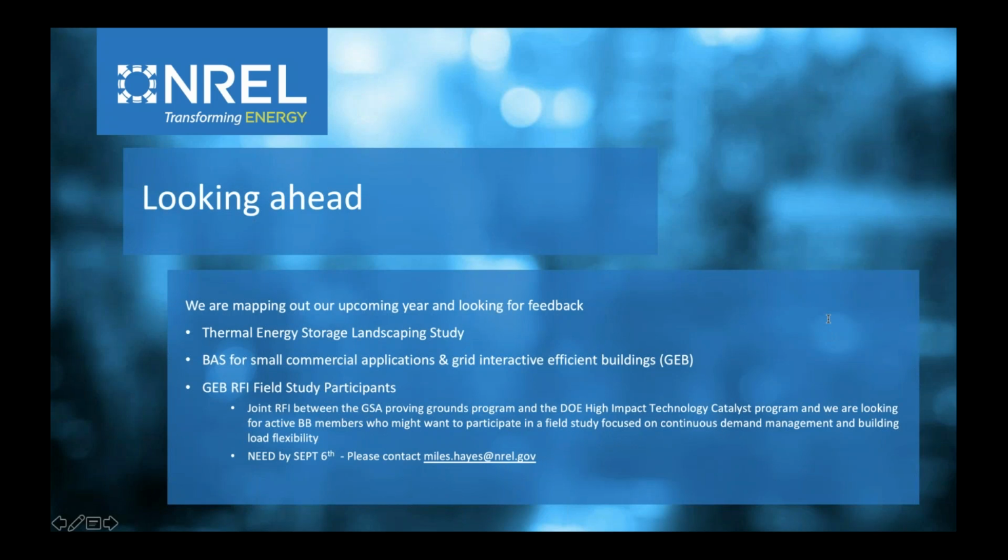The question was, has NREL looked at the combination of solar to reduce demand percentage? So I guess that's maybe more directed at us, but Mark has got a number of solar installations that have been completed in K-12 elementary schools. So I'm not aware of any projects where we looked at demand with just solar. Solar by itself doesn't usually decrease demand. You have to have some kind of storage or very active load management. And usually with that active load management, you end up curtailing services that you don't really want to curtail, but you really need to have that storage to decrease your demand with the solar. Otherwise, it usually doesn't line up.